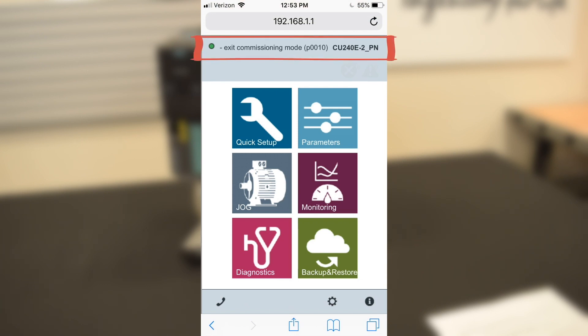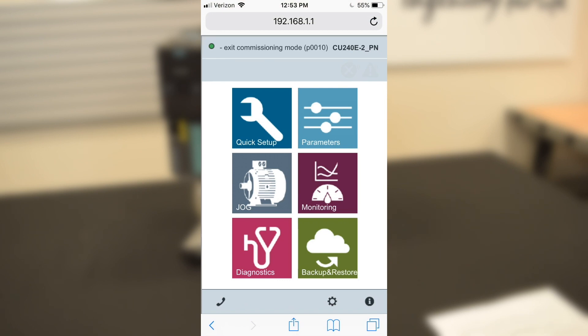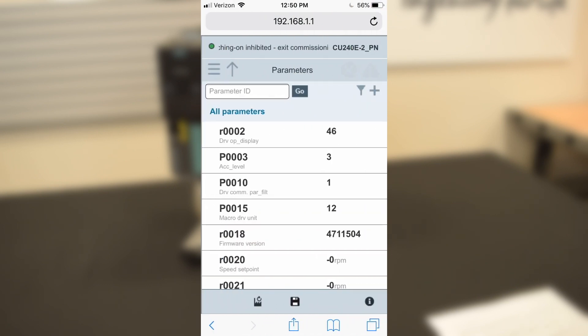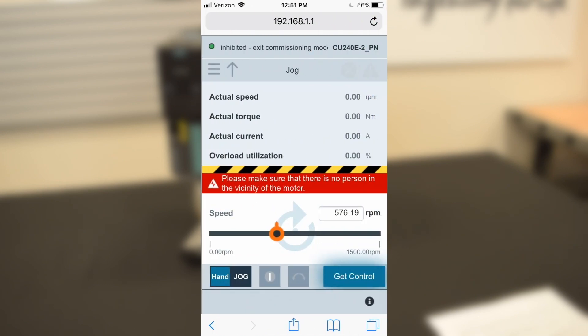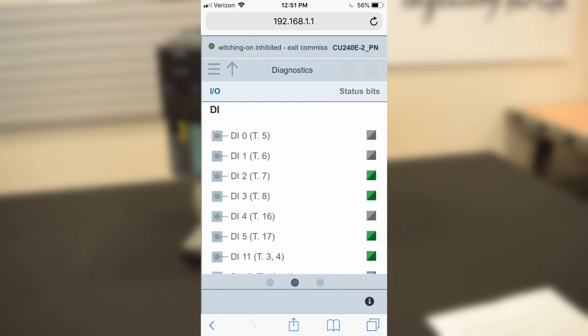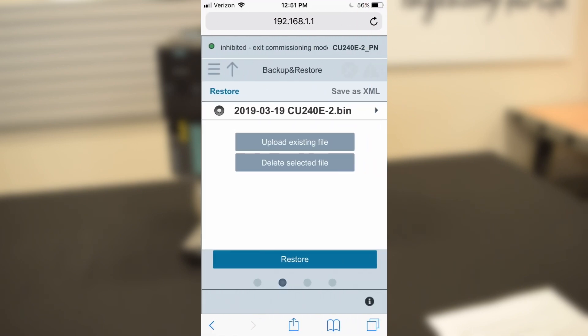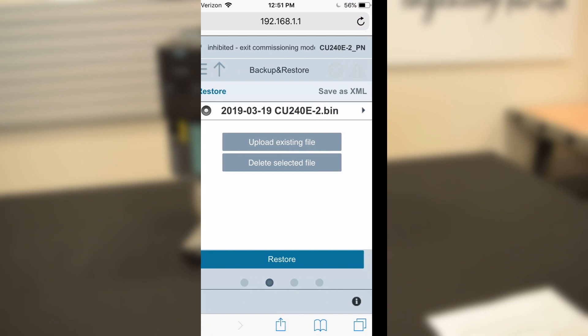Scrolling across the top section is your drive connection status indication and the control unit model you're connected to. The box below that is your fault and alarm indicator. Then we have six tiles to choose from: you can perform a quick setup to commission the connected drive, edit parameters, jog the motor or run it in hand mode, monitor key live motor characteristics, view the diagnostic menu including I/O status, or backup and restore programs to your drive control units.